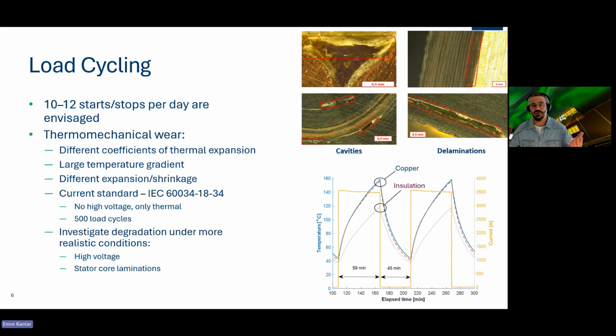As shown earlier, there are temperature changes in the windings and core of the machine. Since the windings consist of different materials - copper and insulation - they have different thermal gradients. So when the temperature changes, due to different thermal coefficients, the insulation material and copper shrink or expand at different rates, which results in cavities and delaminations, as shown to the right.